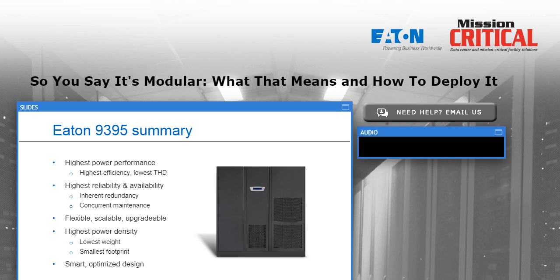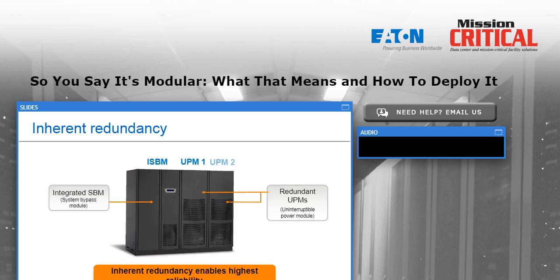I didn't have to buy a whole second UPS with another multi-cabinet battery system and a big chunk of switchgear to tie them together. I simply add an identical 300 kW module, in this case on the left-hand end of the box. And I can do that in the field with a minimum of disruption to data center operations. And now I've got N+1 redundancy until I outgrow that, and I may have the ability to add extra modules down the road. So I can do a little bit of planning for the future, but I don't have to deploy an oversized UPS on day one. So a smart, optimized design that allows the customer the flexibility to grow a little bit or a lot whenever they need to is the hallmark of any modular scalable UPS.